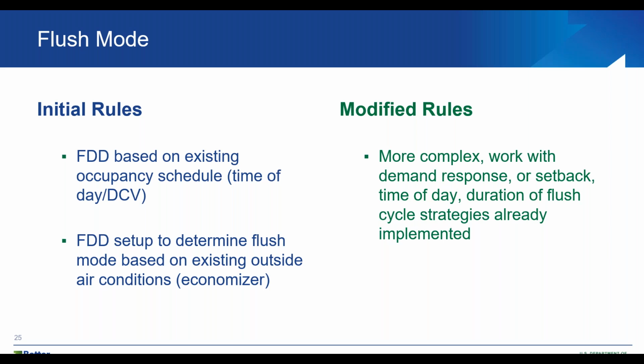So this could be more complicated with modified rules, because there are a lot of systems that are designed for demand response. They're setting back certain times of the day or even at nighttime, and we want to make sure they all work together. So if you had a demand response one where you would normally reduce the amount of outside air, this is a case where you might be doing the opposite. So you'd want to not look for the demand response. You'd want to be looking for flush cycle and what the new ones that are implemented are.